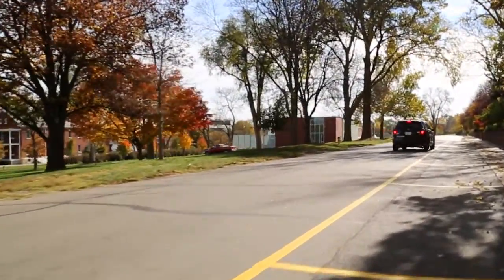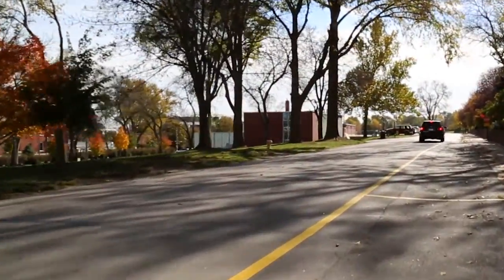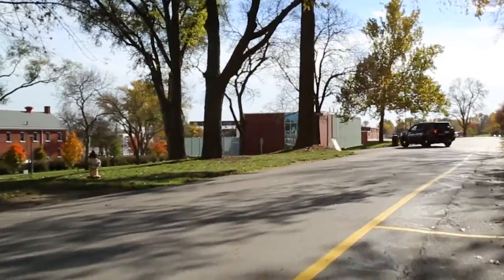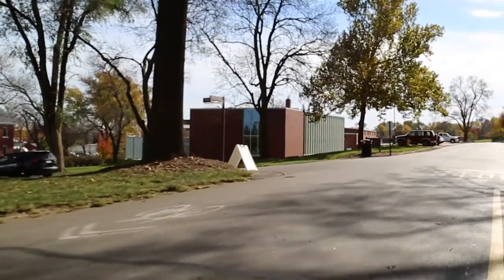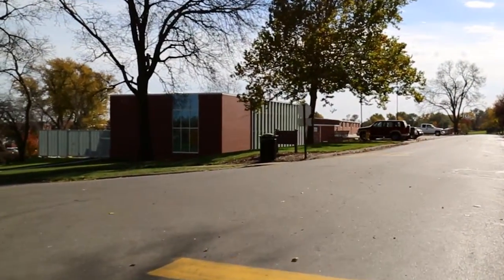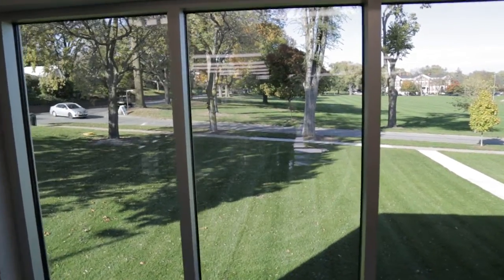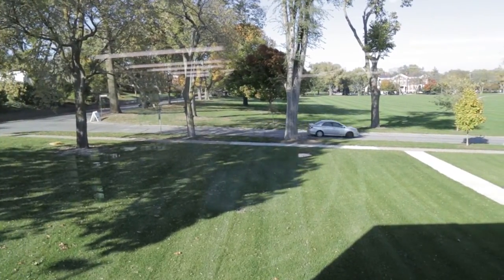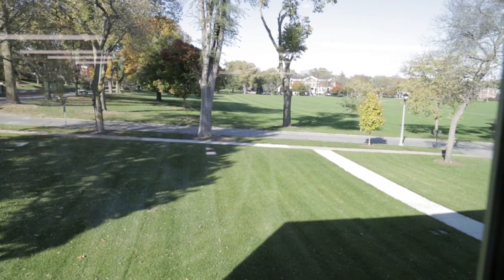Now, the reason that this central utility plant is located slightly remotely from these buildings is because it's actually located up next to our Fort Omaha, the center of the campus, up by our parade ground, right across the street from where we're speaking. The reason it's there is because we tested the capacity underneath the parade ground to bring on ground loop water to serve the central plant. So down the road, if the college wants to, we can put in geothermal wells underneath our parade ground and connect them to this central plant to save even more energy. That adjacency to the parade ground is how this building got placed where it is, thus this extra bay of space for that future technology.